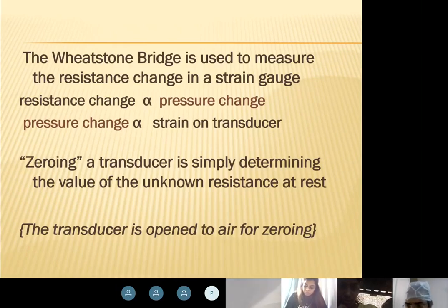...now the transducer knows this is zero. That is what we are doing with zeroing. That means we are turning the stopcock so that the transducer is exposed to the atmosphere, and then you go to the monitor and press zero. That means you are telling the transducer this is zero pressure. So the moment you change the stopcock, whatever ripples come from the water will be taken as whatever pressure it is supposed to be.